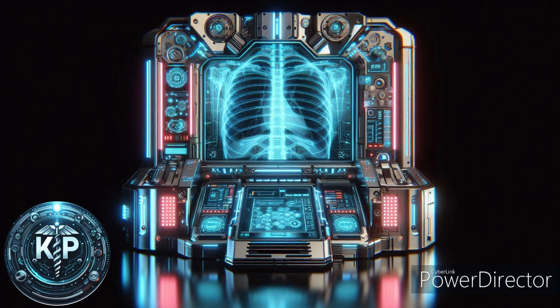X-ray tube maintenance, technical approach: address common tube issues: cathode filament failure, tube arcing, anode failure, glass housing cracks or oil leaks, rotor bearing failure. High voltage generator, technical approach: regularly inspect and maintain the generator. Address voltage fluctuations promptly using specialized equipment.